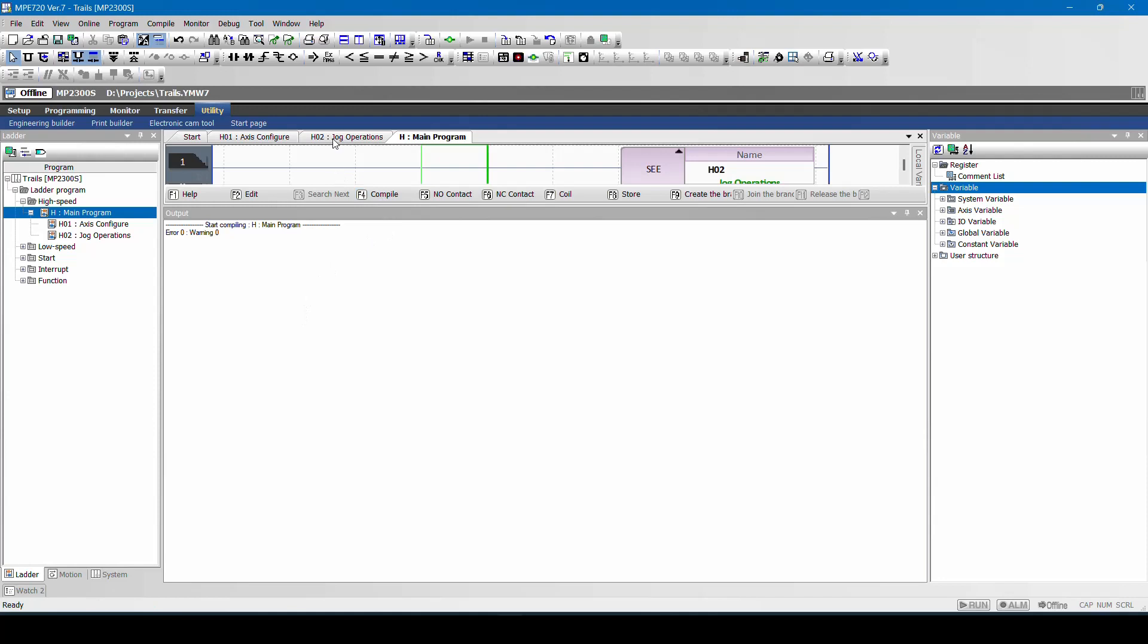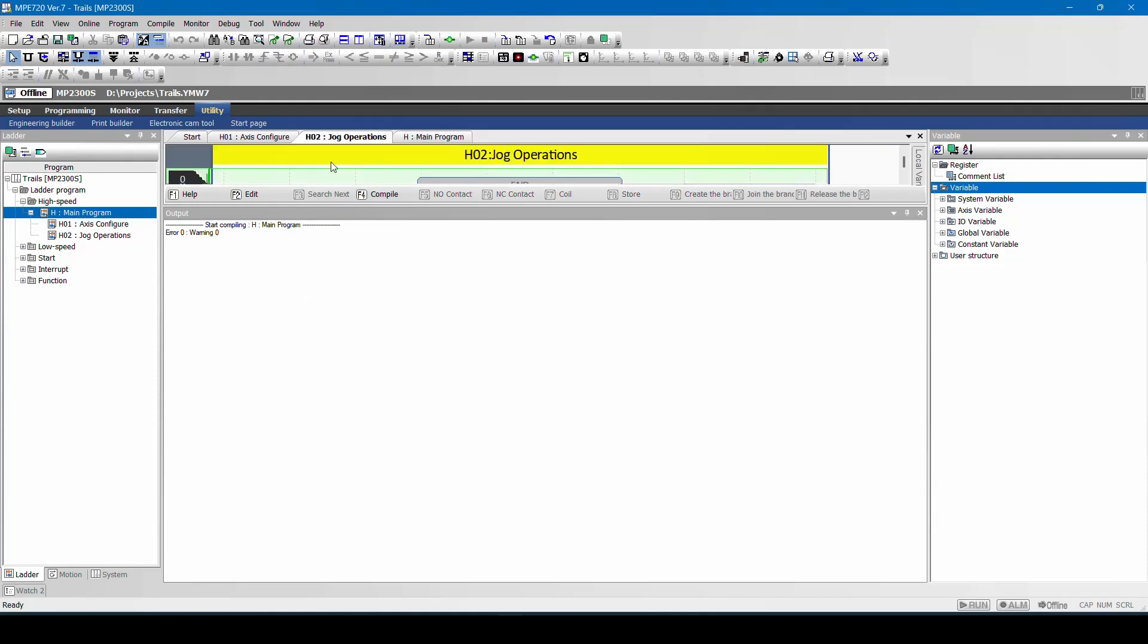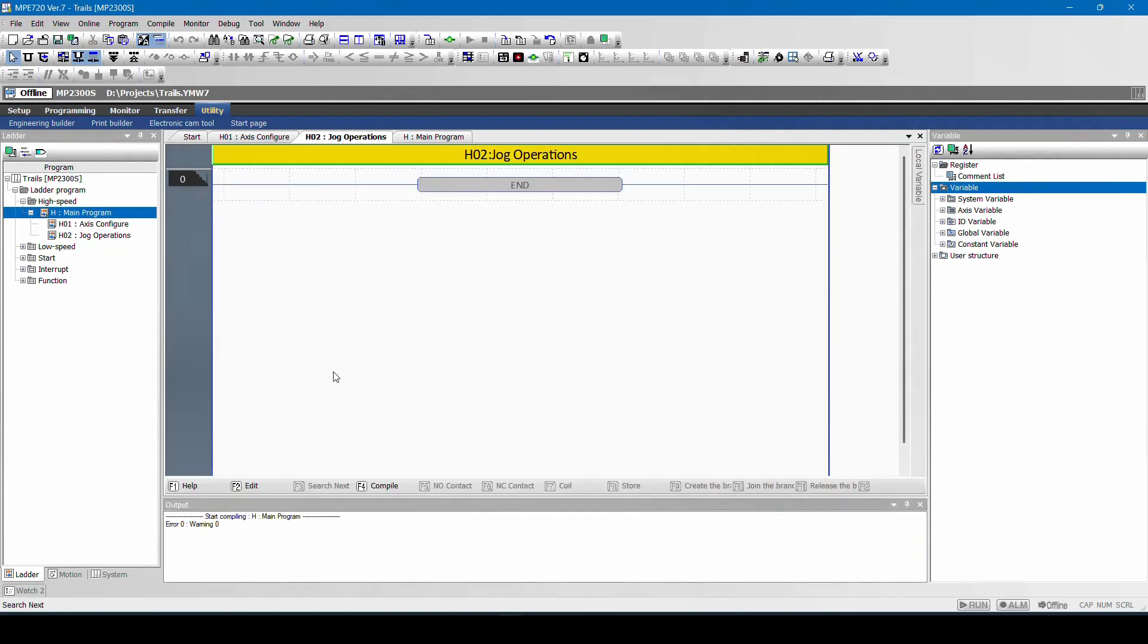So now I have to do the basic jog operation. What we will do is we will try to take two digital inputs, one for jog forward and one for jog reverse, and we will try to give the command code. Command code is the code number used to denominate the motion command given to the drive through controller. So there are different control methods. One of them is jog mode.